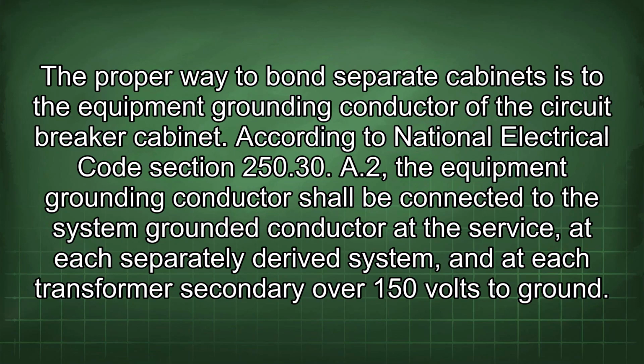The proper way to bond separate cabinets is to the equipment grounding conductor of the circuit breaker cabinet. According to National Electrical Code Section 250.30(A)(2), the equipment grounding conductor shall be connected to the system grounded conductor of the service, at each separately derived system, and at each transformer secondary over 150 volts to ground.